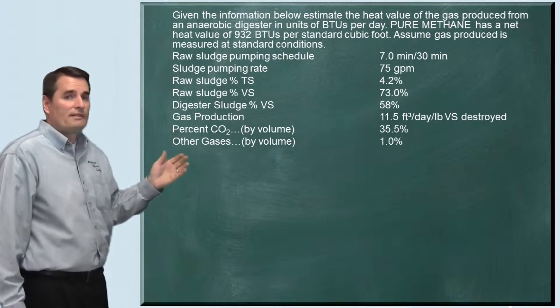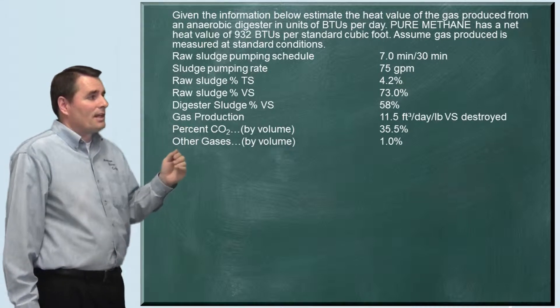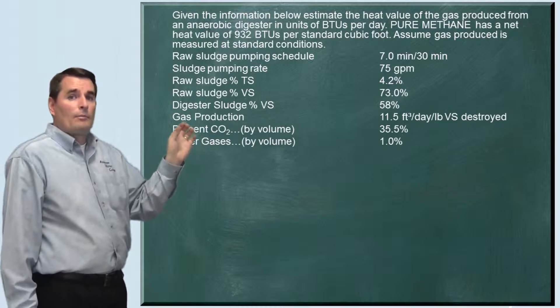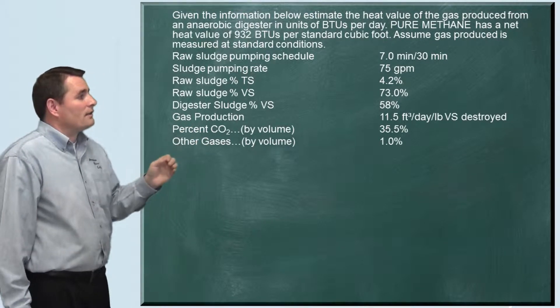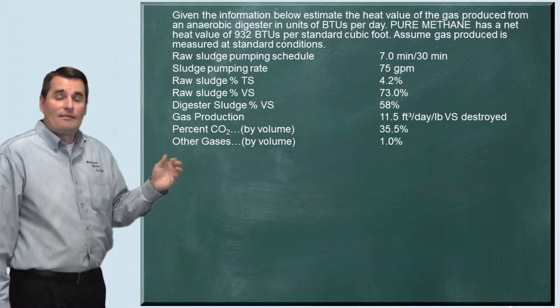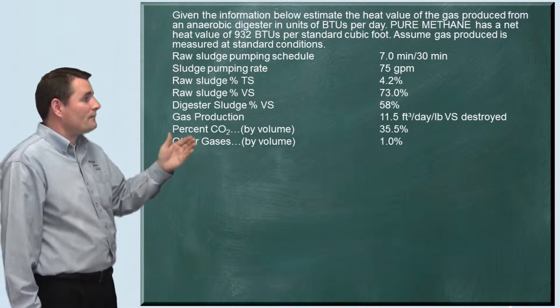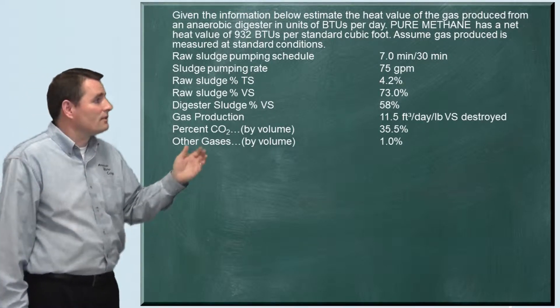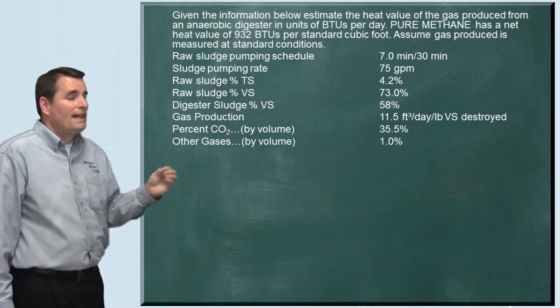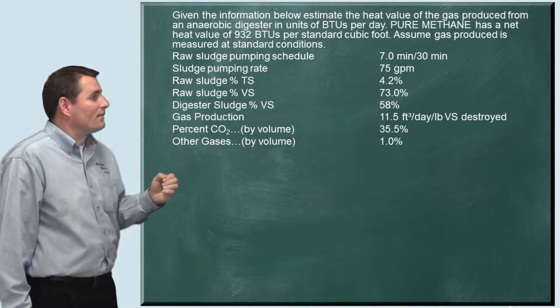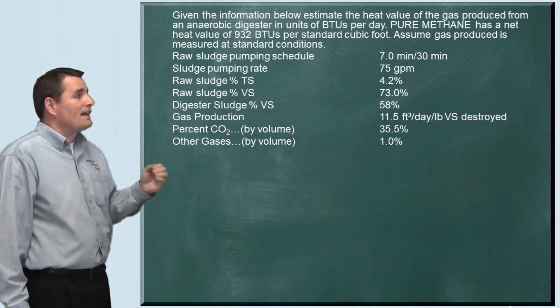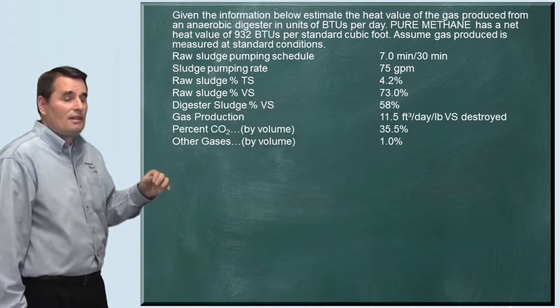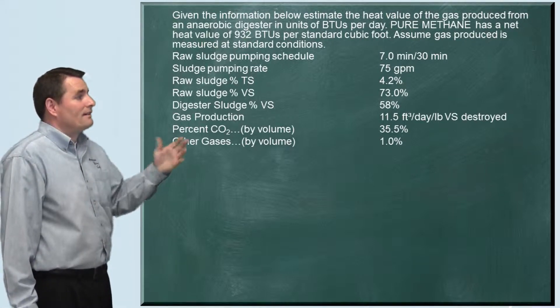They gave us the raw sludge pumping schedule: 7 minutes every 30 minutes, meaning for every half hour they're pumping for 7 minutes. The sludge pumping rate is 75 gallons per minute. They also gave us the total and volatile solids for the raw sludge: total solids of 4.2% and the volatile percent is 73.